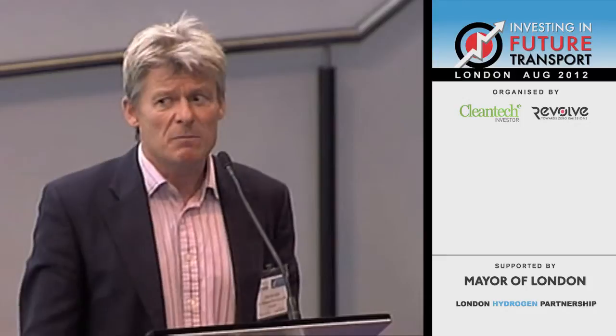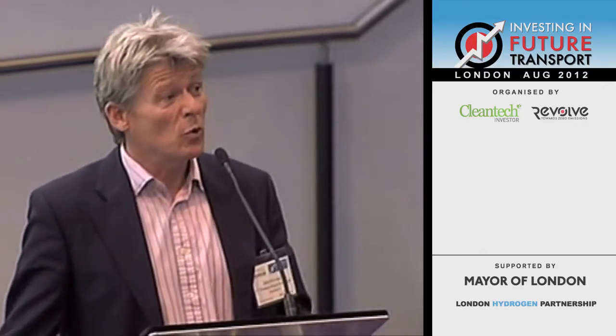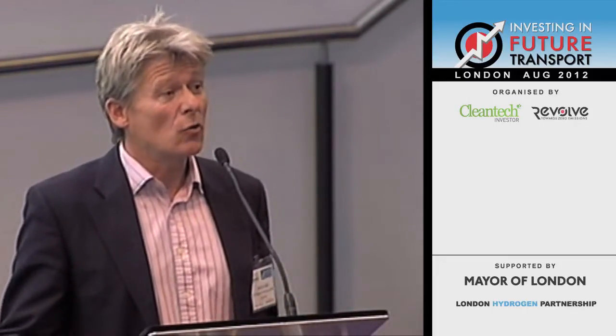I want to talk a little bit about locations and where to put this sort of infrastructure. If you put it on highways, that's typically 100 amps — that's not easily available. Only 20% of locations have 100 amp availability. But looking at destinations such as shopping malls, clubs, bars, restaurants — anywhere you go typically for an hour — we could have technology that's under £10,000 that would use only a 32 amp supply and can charge in under 30 minutes from 30% to 80% state of charge. So it's affordable, it's available now, and it can be installed at just about any location with existing grid technology.